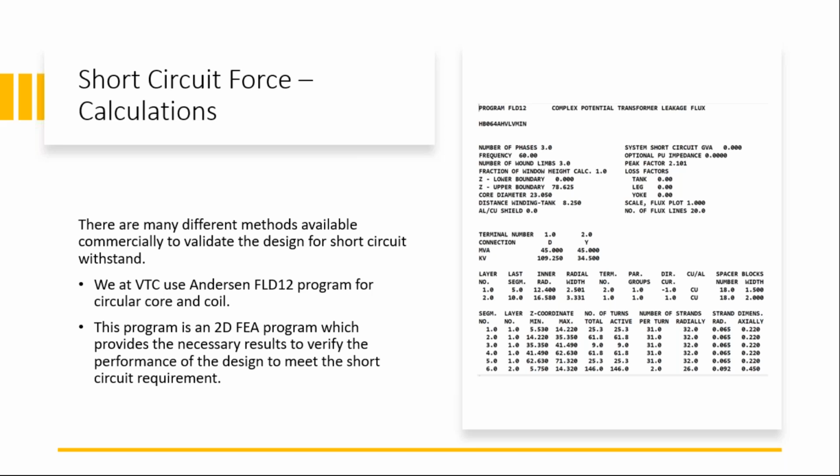And at VTC, we use the Andersen program to do the short circuit force calculations. And this program is, as we know, a 2D finite element based program. So it gives certain results, and those results will be used to derive the force parameters to evaluate with respect to the standards.